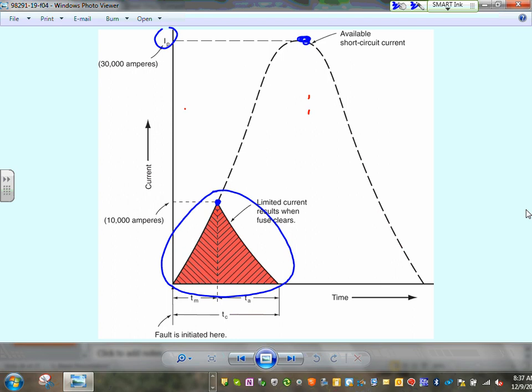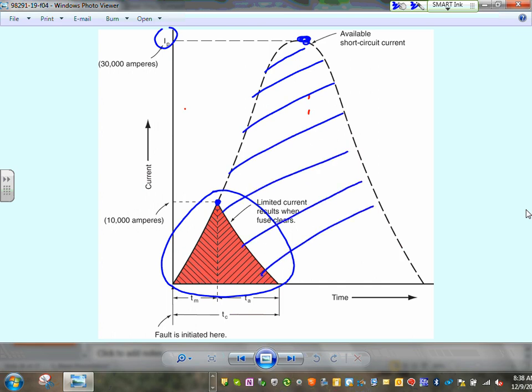Why is a current limit fuse limiting? This is the amount of energy that can get through. Versus if you don't have current limiting fuses, all this will be the amount of energy that your equipment will be encountering. Who cares? One word: current. Your equipment will not be shaken or baked as much. Any comments, guys? Any questions? So when you see current limit fuses, they open so fast that your equipment will not be shaken or baked as much.